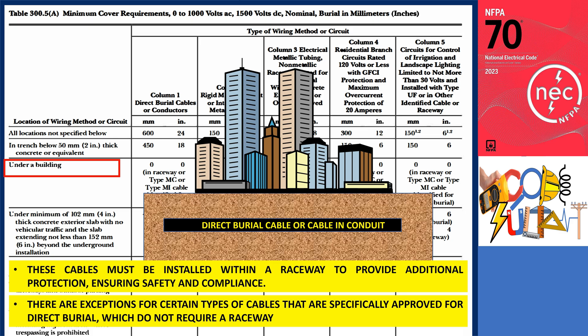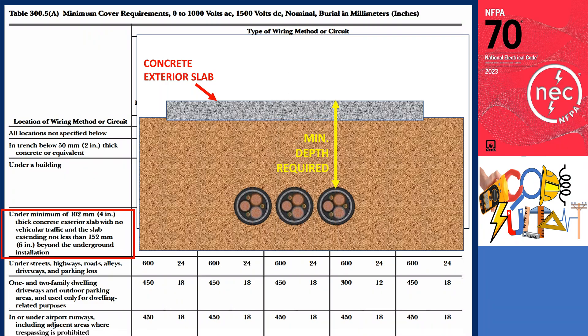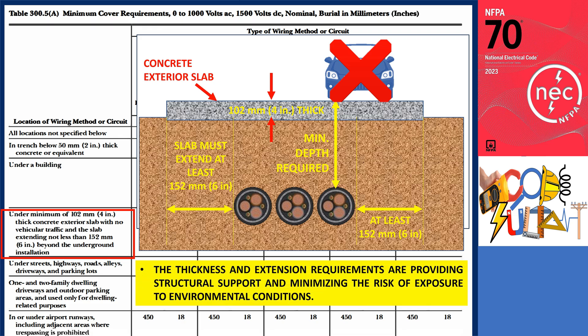The fourth location type involves the installation of wiring beneath a concrete exterior slab. For compliance, the slab must be at least 102 millimeters (4 inches) thick and designed to withstand no vehicular traffic. Additionally, the slab must extend at least 152 millimeters (6 inches) beyond the area of the underground wiring. These thickness and extension requirements are crucial for providing structural support and minimizing the risk of exposure to environmental conditions.